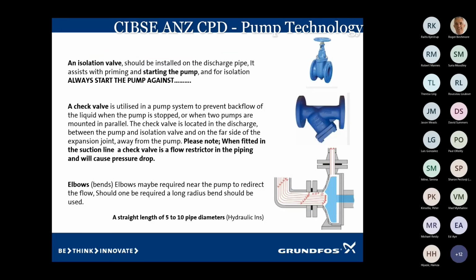So valving, we need to have those set back from the pump. Again, it's a huge turbulence. Strainers, we like to keep those away from the pump as well. And also remember, if the strainer's on the suction part of the pump, it will get blocked, and there's a possibility that the screen will block and that could starve the pump.